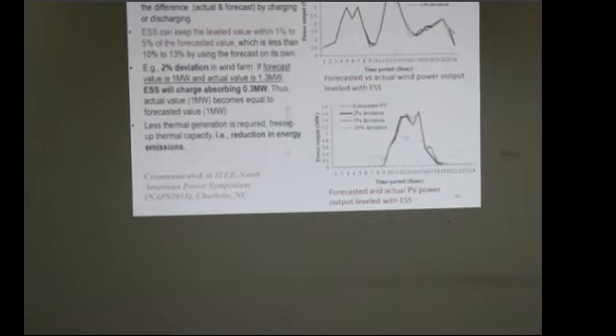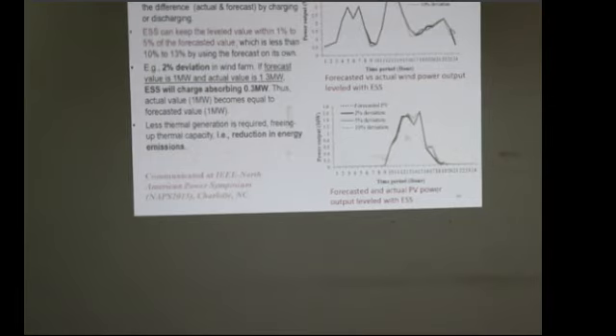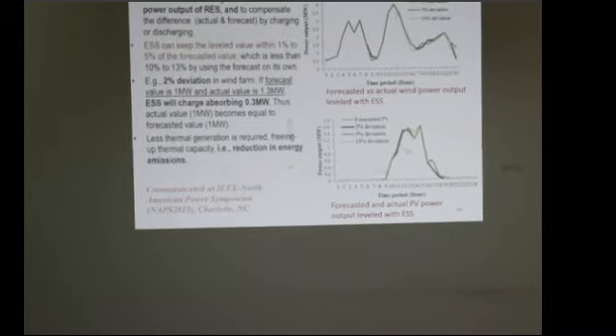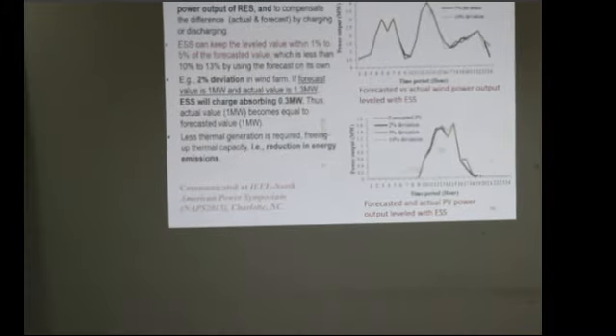So what actually happens is I integrate a storage system into my grid or microgrid. I forecast the power, and I utilize the energy storage to match the forecast with the actual value. For example, I had a forecast of 28.5 whereas the actual was 28. So I will hook up an energy storage device there and try to make the forecasting very close to actual. That is called leveling of the actual with the forecasting - one of the areas we work on in my lab.